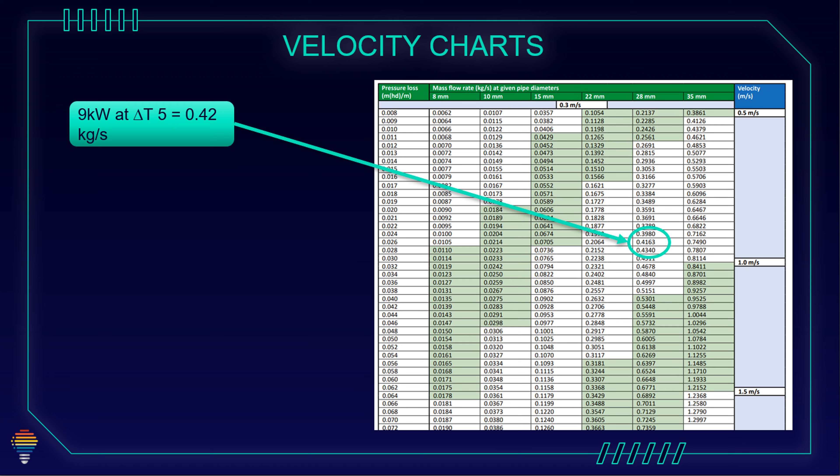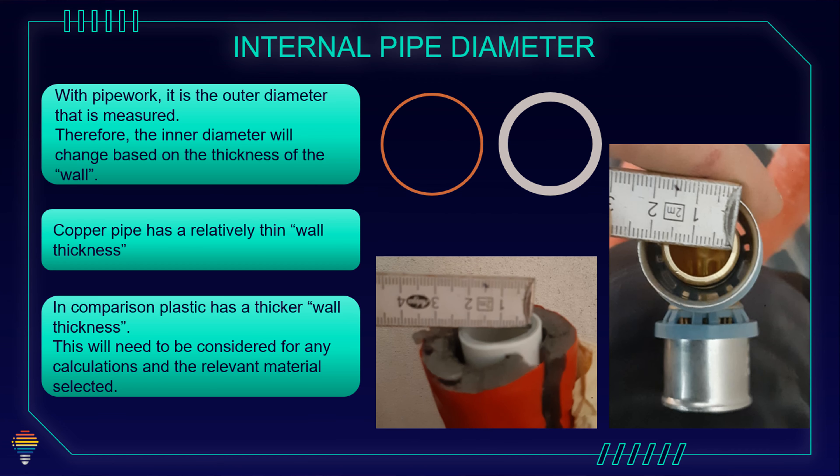We need to say that this table is for copper pipes. Copper pipes have thinner surface than plastic pipes, so if we want to go with this flow rate and with this velocity on plastic pipes, we need to go one size bigger, so 35 for example if we have plastic pipes.